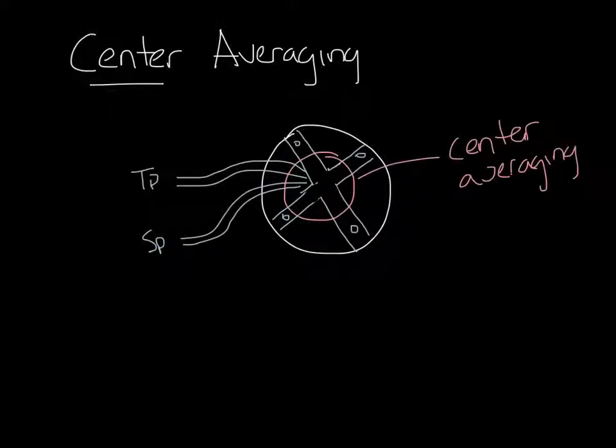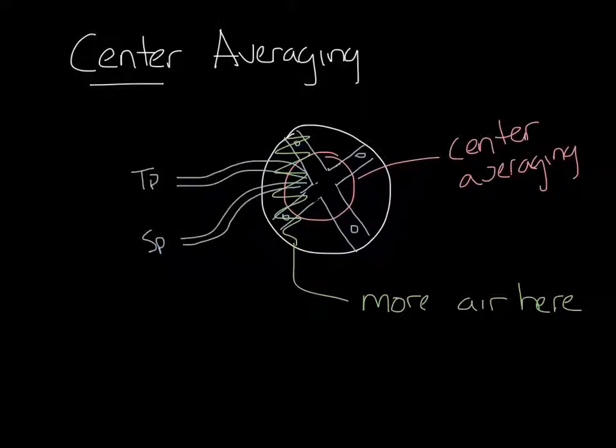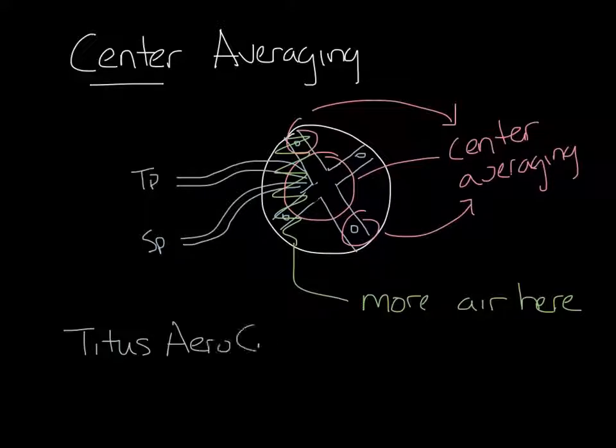Now if there are poor inlet conditions and the air piles up on the left side of the inlet like it did in the last one in this green area, the readings from the hole on the left, which is reading high, and the hole on the right, which is reading low, are going to be averaged in the center of the flow sensor and give a more accurate signal to the controller. This means that VAV boxes with center averaging flow sensors like the Titus AeroCross are not affected by poor inlet conditions as much as linear averaging sensors are.